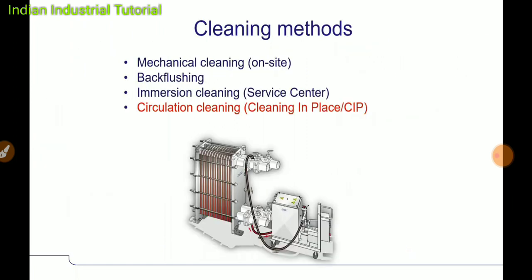These are the cleaning methods. One is backflushing, which we have seen in earlier slides. Mechanical cleaning at your site, where we open the heat exchanger and clean it. Immersion cleaning at the service center, where we keep all the plates immersed in a tank with various chemicals suitable for the plate as well as the gasket. We clean those plates completely, as good as new, repair those plates and send them back to you.